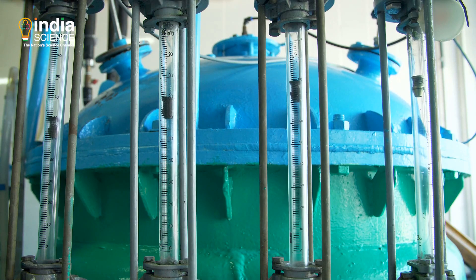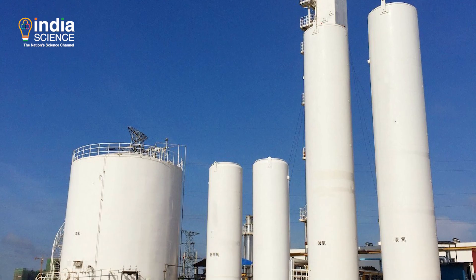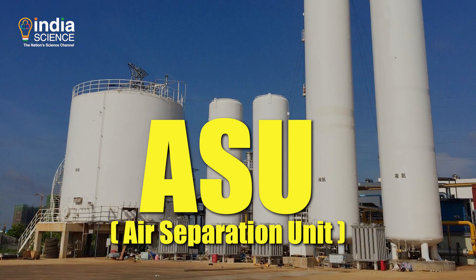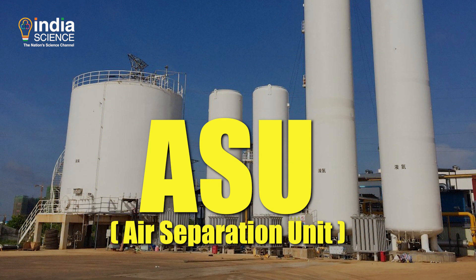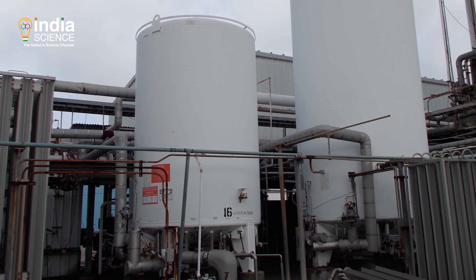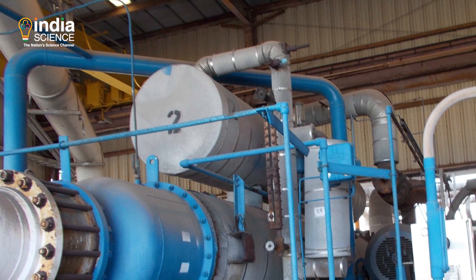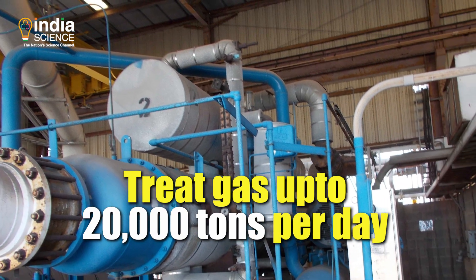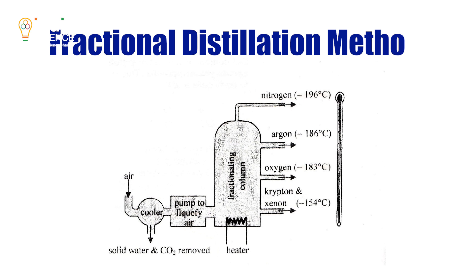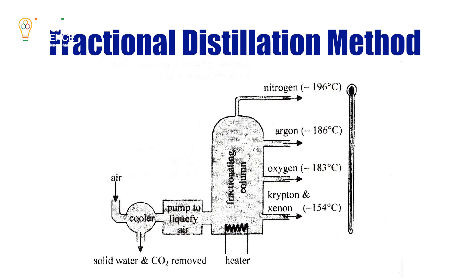There are several methods to produce medical oxygen. The most common commercial method is the separation of air in an Air Separation Unit, or ASU. ASUs are plants that treat large volumes of gas, from a few hundred tons to 20,000 tons per day. ASUs use a method called the fractional distillation method to produce pure oxygen.